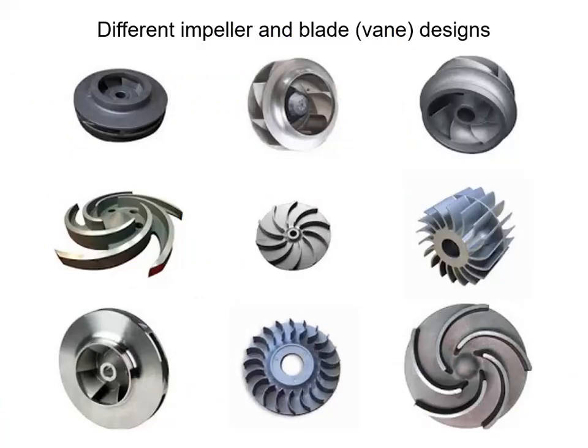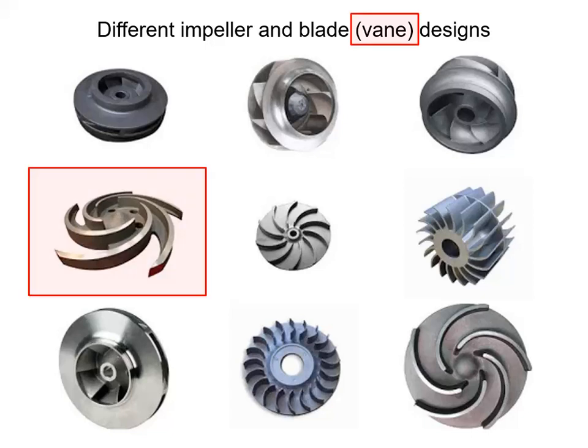Here you see a number of different impeller and blade designs. Note that the blades of a centrifugal pump are also called vanes. This design, for example, has no impeller disc. Both sides of the blades are open. If the blades rotate in this direction, it is called a backward curved design. If they rotate in the other way, it becomes a forward curved design.